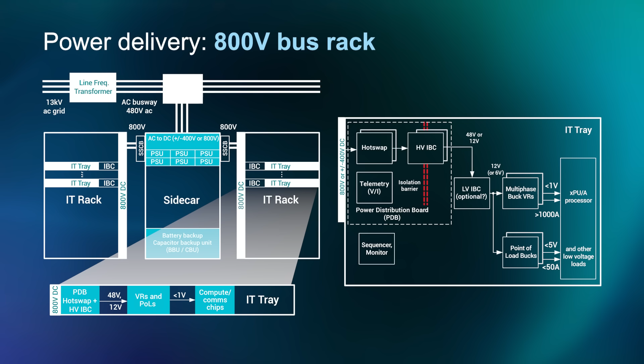So now that we understand the high-level architecture, what are the technical challenges to getting to 1 megawatt racks? One of the key challenges is overall grid-to-gate efficiency. Any power that's lost in energy conversion generates heat, and it doesn't go towards the intended compute load. Another key challenge that goes hand in hand with efficiency is power density. Space is limited and power levels are only going up, so this forces the need for increased power density. Performance is also critical. There are large load transients in these systems, and fast response is necessary.